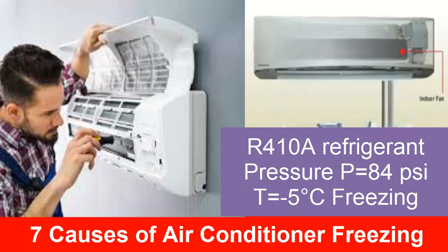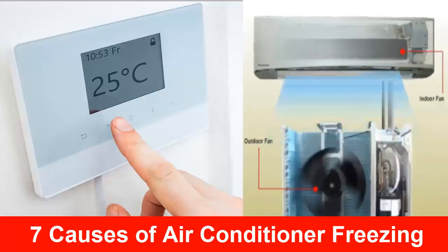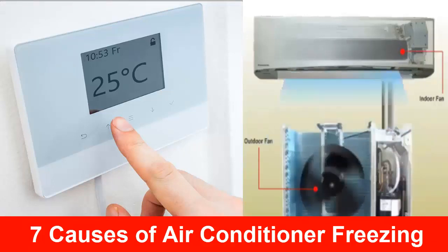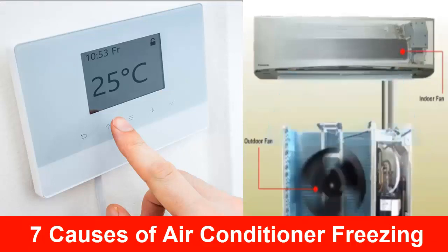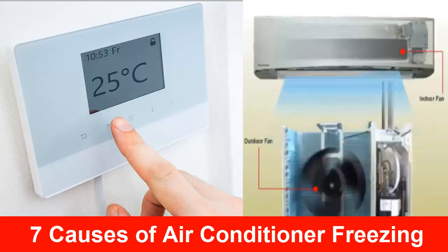2. Disconnected or bridged thermostat. If the unit uses a thermostat, and it is disconnected or broken, the air conditioner will never turn off. This can cause the unit to freeze, especially at night when the outdoor ambient temperatures are lower.